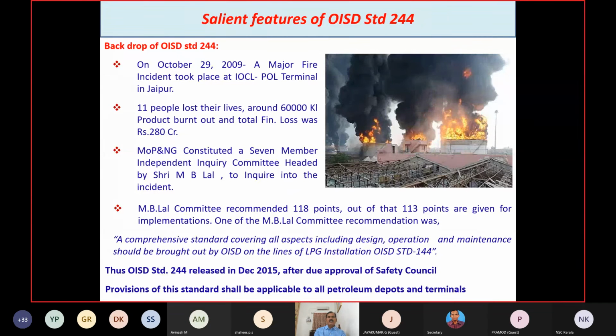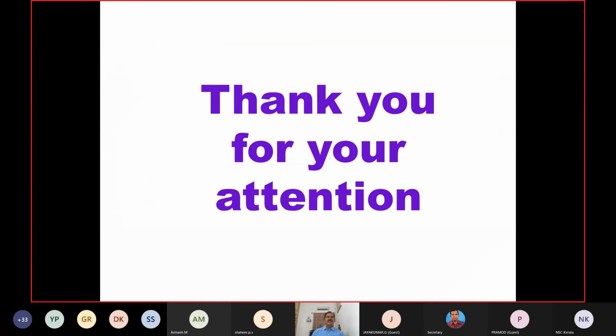One of the M.B. Lal committee recommendations was that a comprehensive standard covering all aspects, including design, operation and maintenance, should be brought out by OISD in line with the LPG installation standard, OISD standard 144. That's why I'm telling it's a role model standard. Thus OISD standard 244 was released in December 2015 after due approval of the Safety Council. The provisions of the standard shall be applicable to all petroleum depots and terminals. So if you go through 244, you can understand about the storage and handling of petroleum products in a POL terminal. I hope you will understand all this. Now we come to the end. Thank you for your attention, sir.